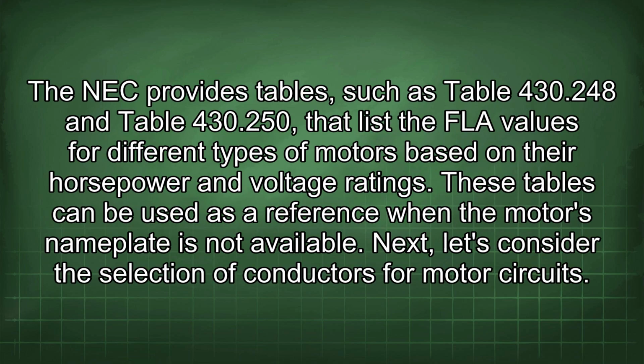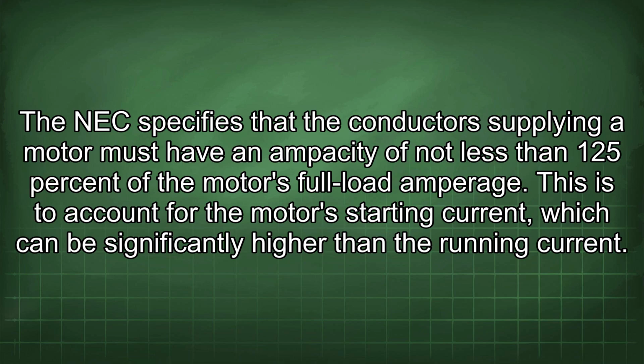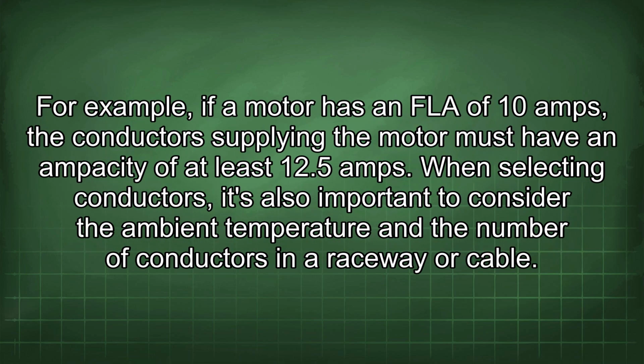The NEC provides tables such as Table 430.248 and Table 430.250 that list the FLA values for different types of motors based on their horsepower and voltage ratings. These tables can be used as a reference when the motor's nameplate is not available. Next, let's consider the selection of conductors for motor circuits. The NEC specifies that the conductors supplying a motor must have an ampacity of not less than 125% of the motor's full load amperage. This is to account for the motor's starting current, which can be significantly higher than the running current. For example, if a motor has an FLA of 10 amps, the conductors supplying the motor must have an ampacity of at least 12.5 amps.